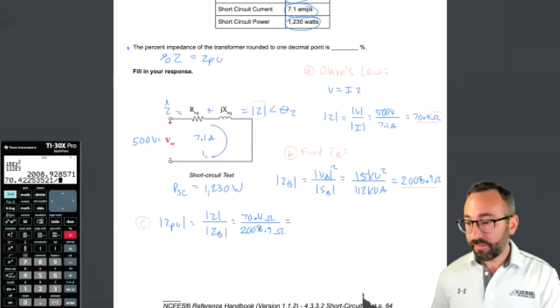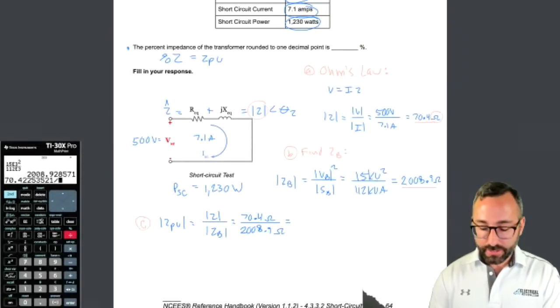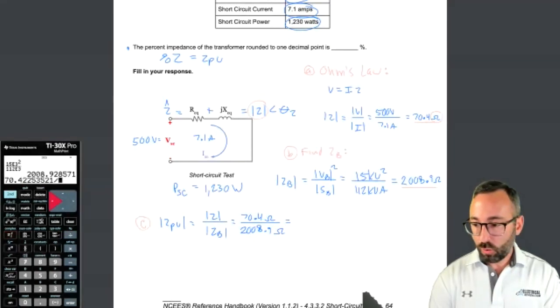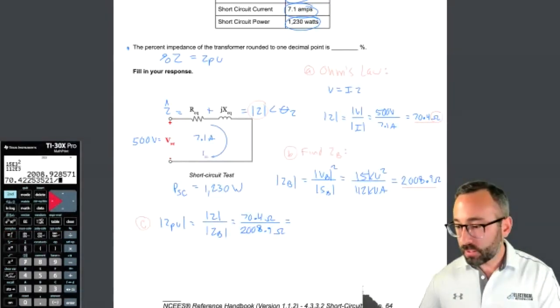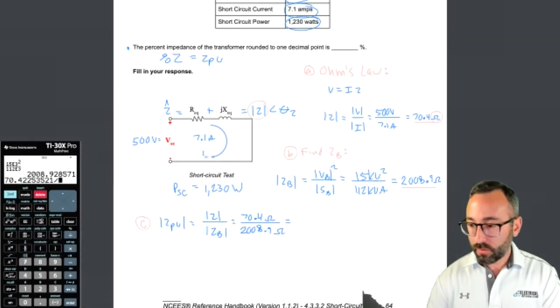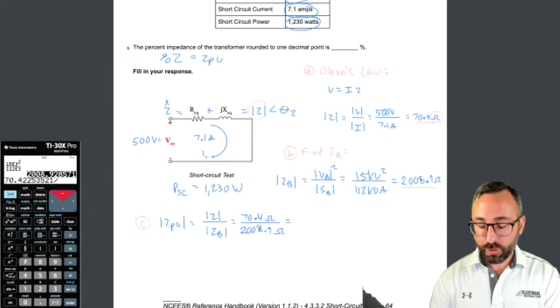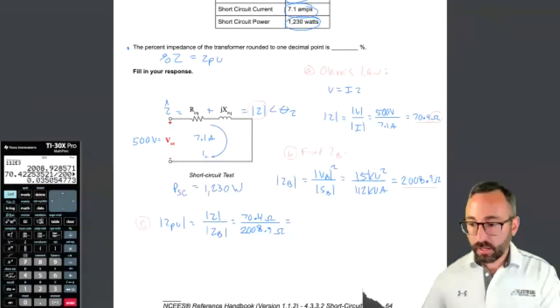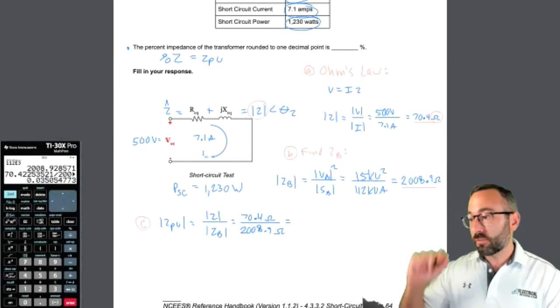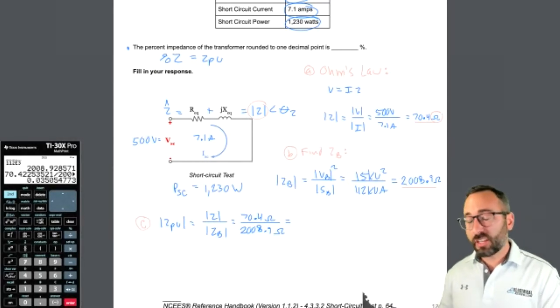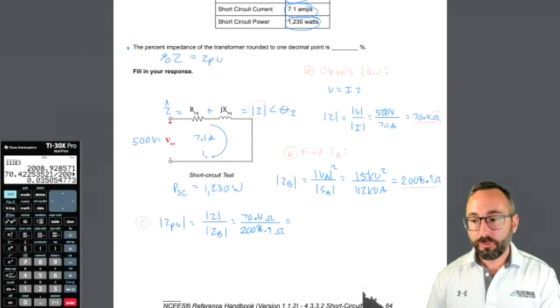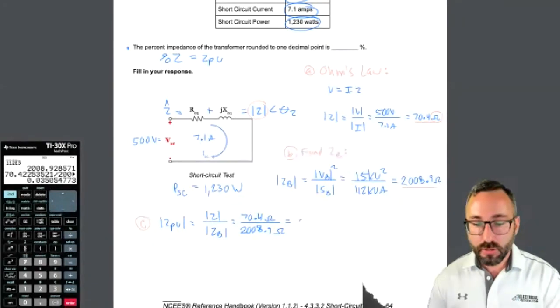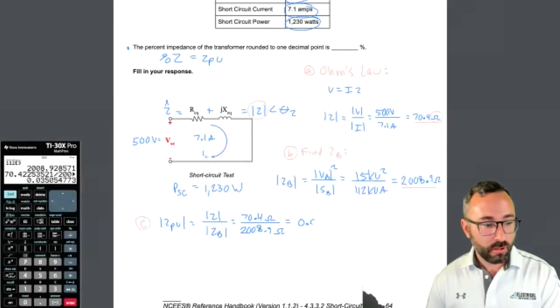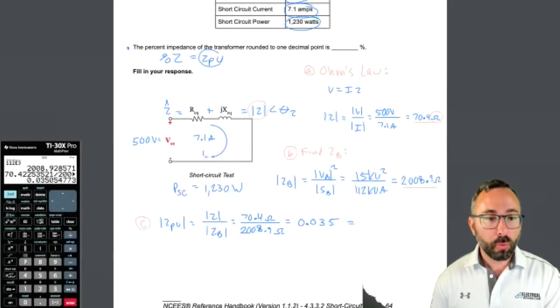I'm going to hit the divide button, and then I can either do second answer, not pi, or I can scroll up. Let me delete that pi. Or I can scroll up, grab the base impedance value by pressing enter when it's highlighted. Ta-da! We just use our calculator to do the heavy lifting for us without having to type in just 70.4, just 2008.9 for full accuracy. So the per unit impedance is 0.035. And then remember, we don't want it in per unit form. We want it in percent impedance.